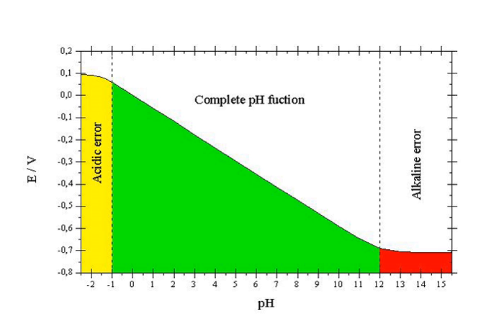All glass pH electrodes have extremely high electric resistance from 50 to 500 megaohms. Therefore, the glass electrode can be used only with a high input impedance measuring device like a pH meter, or more generically, a high input impedance voltmeter which is called an electrometer.